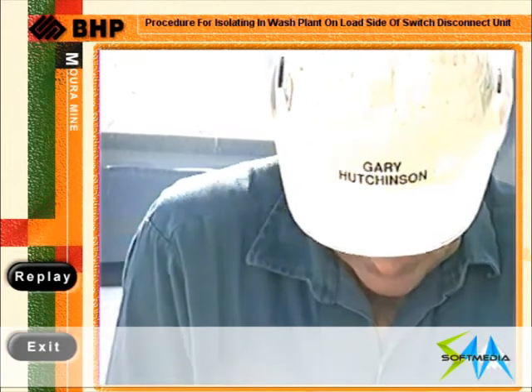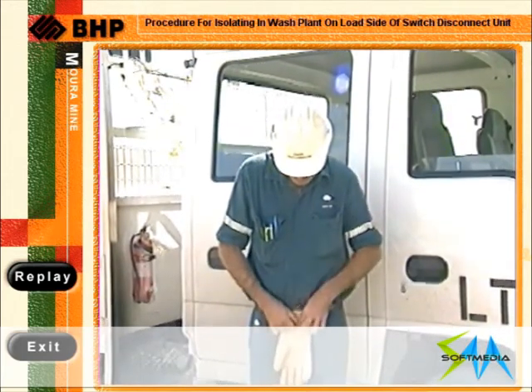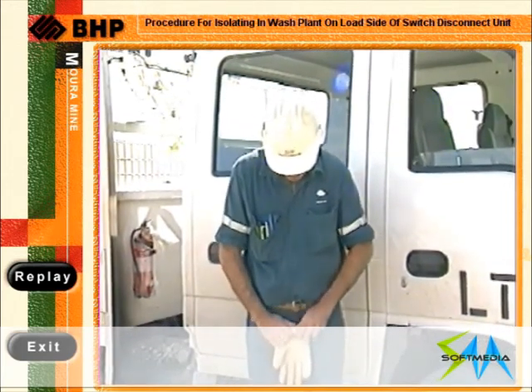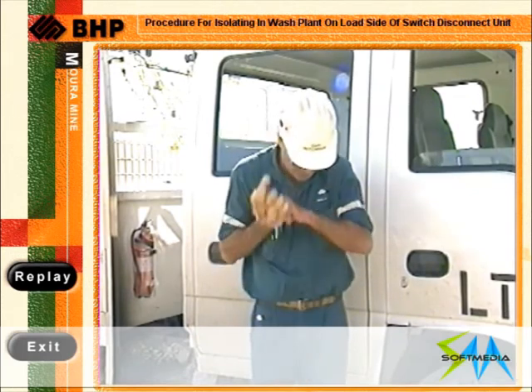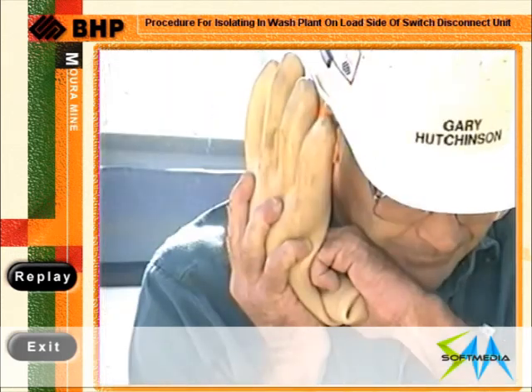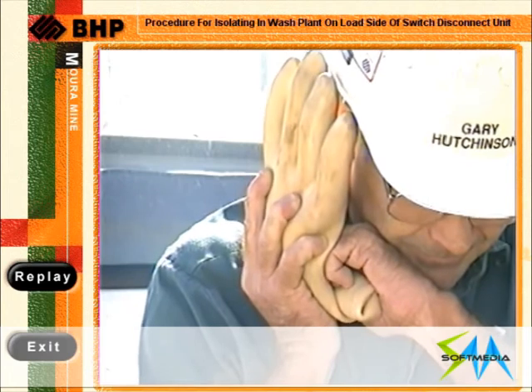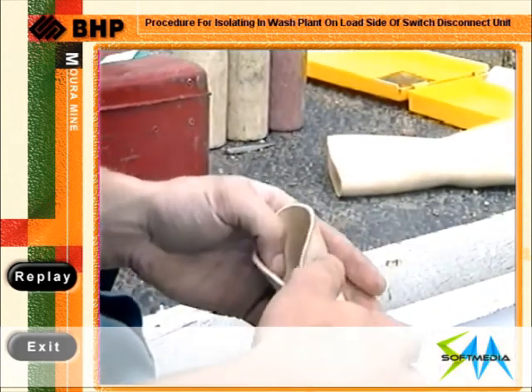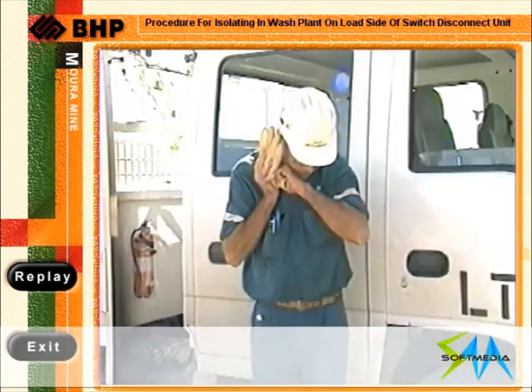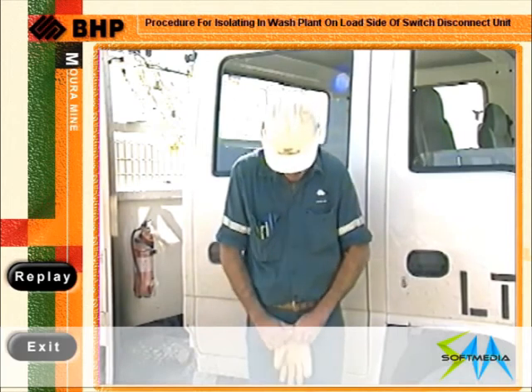You must roll up the high voltage gloves to test for air leakage. If air leaks, it means they are damaged and you are not to use them. You must also check for obvious deterioration, such as cracks, perished rubber, stiffness, or gloves bonded together.